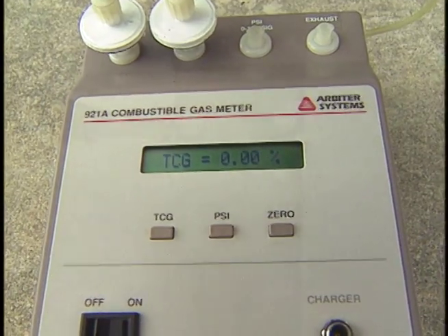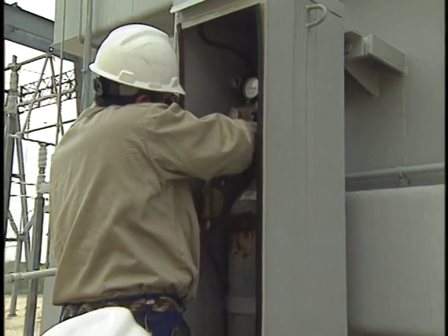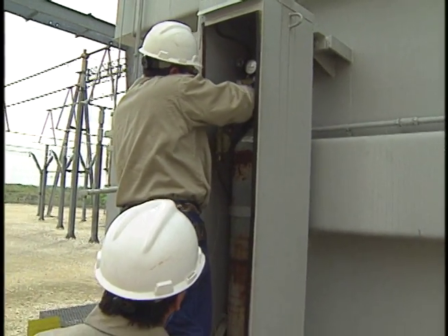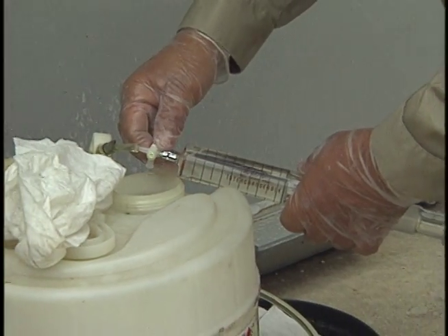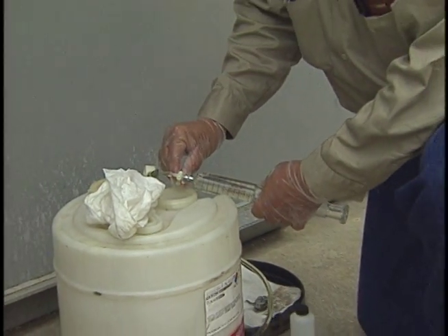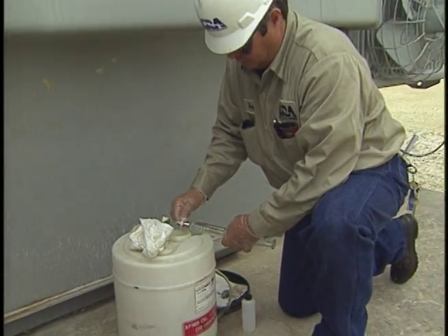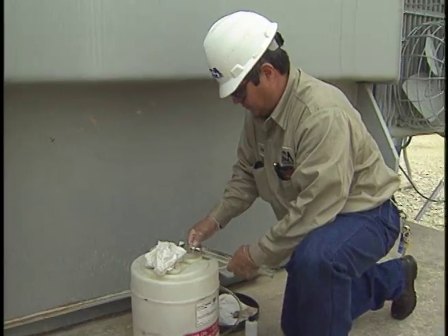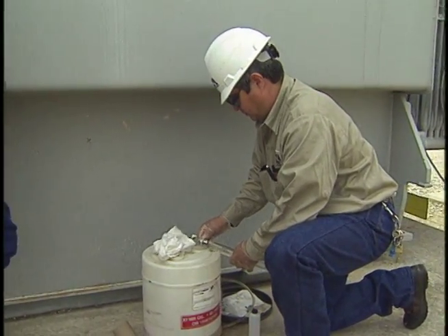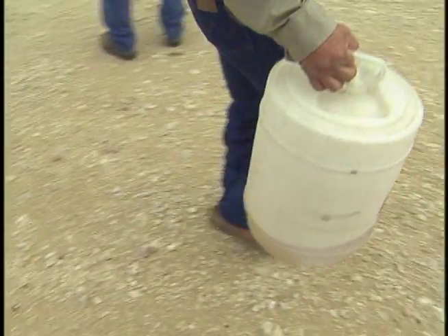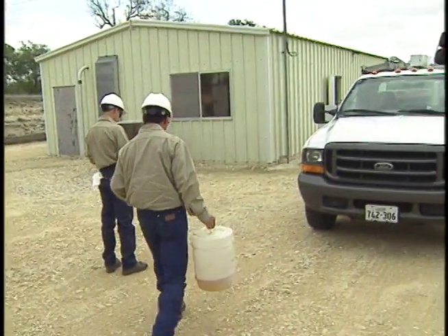Crews also analyze gas samples from inside the transformer, which can indicate electrical arcing. If the gas reading is abnormal, they will then draw an oil sample for more precise lab analysis. Normally we go along and don't see anything, but then all of a sudden, boom, we find a reading, and it's a real flag. It indicates that we've got something going on.